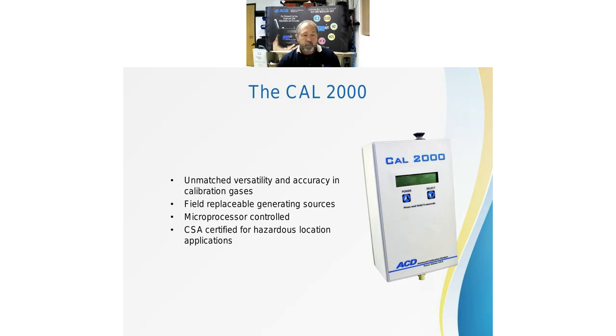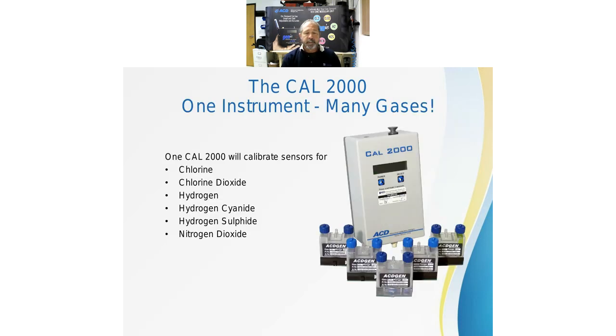I'll show you next what the generating sources that plug in look like. I think that's the first picture I've had of those. But those insert into the unit, and then each one of them has a memory chip. When you put it in the instrument and turn it on, it tells you how much life is left on that particular generating cell, and the instrument reads it and knows what polarity to set the cell at to generate the gas you want, and how much current to pass when you tell it what concentration and flow rate you want.